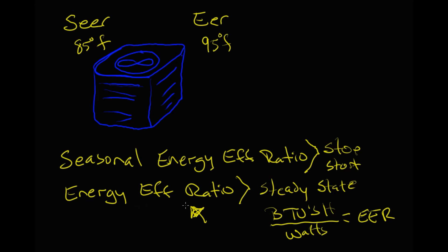The problem being, though, that it's going to be based on whatever temperature I take at that time. If it's cooler than 95, I'm going to have a higher EER than it was rated with. If it's warmer than 95 degrees, it's going to be a lower EER. But I can measure it and I can actually show the customer, especially if we're close to the 95. We can usually typically see that it's actually producing the EER that it was designed to do.